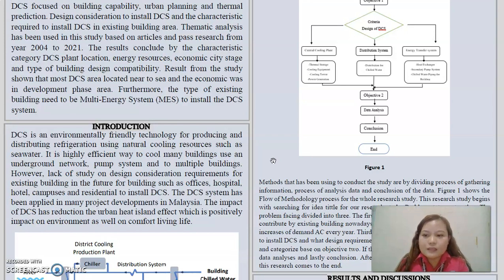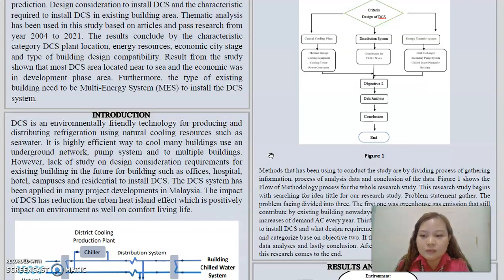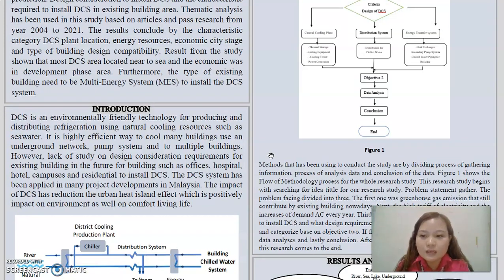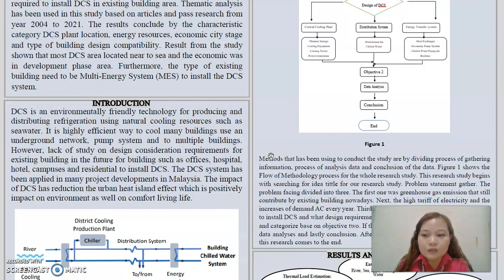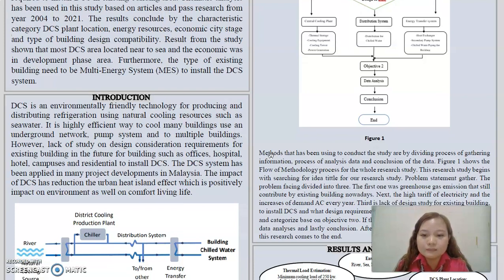Furthermore, the type of existing building needs a multi-energy system to install DCS. DCS is an environmentally friendly technology for producing and distributing refrigerant using natural cooling resources such as seawater. It is a highly efficient way to cool many buildings using underground network pump systems connected to multiple buildings. However, there is a lack of study on design consideration requirements for existing buildings such as offices, hospitals, hotels, campuses, and residential buildings to install DCS.